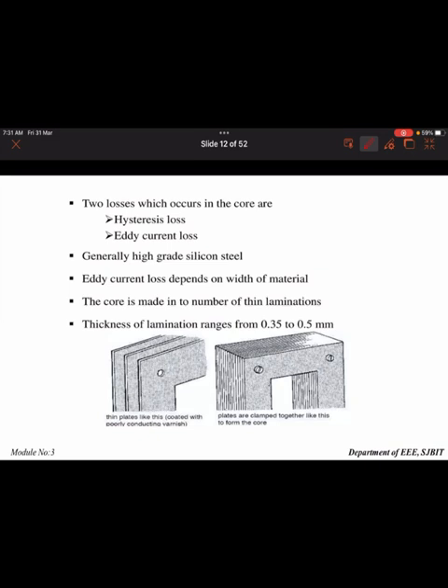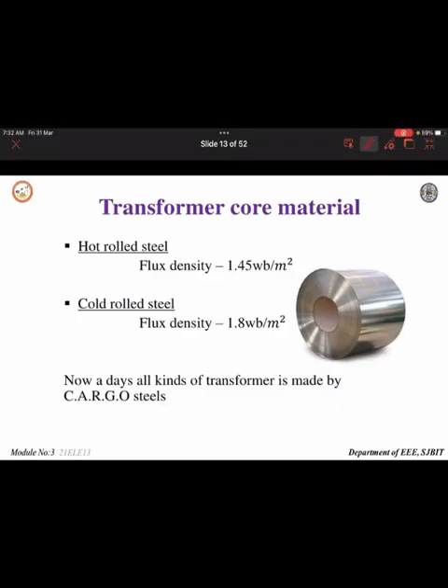There are two types of losses in the core: hysteresis loss and eddy current loss. High-grade silicon steel material is used to make the core. Eddy current loss depends on the width of the material. The core is made up of thin laminations with a thickness in the range of 0.35 to 0.5 mm. Between the thin laminations there is insulation, and they are pressed together to form the core. The transformer core material is hot-rolled steel or cold-rolled steel.